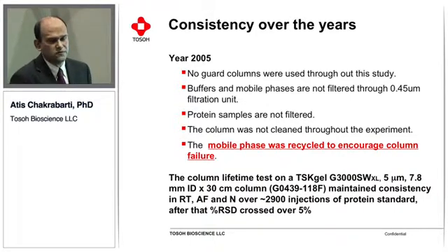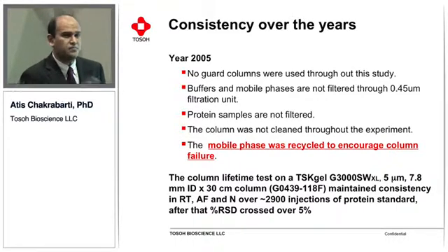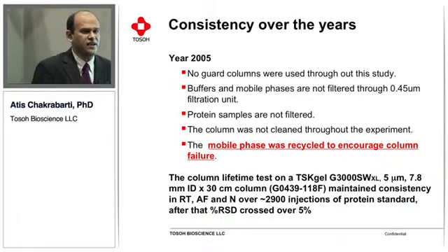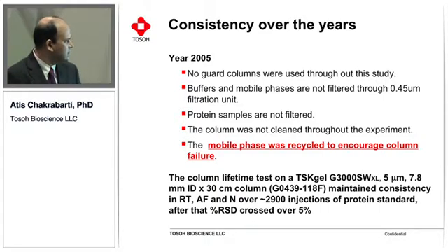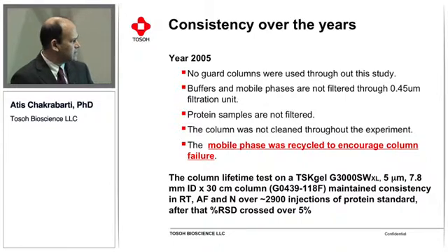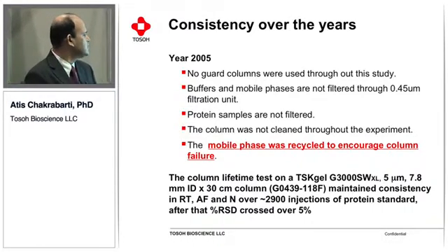Protein samples were also not filtered. The column was not cleaned, and in that study the mobile phase was recycled to give some more pressure on the column. And as you see, the column lifetime test was excellent, and retention time, asymmetric factor, and efficiency over 3,000 injections were very good.